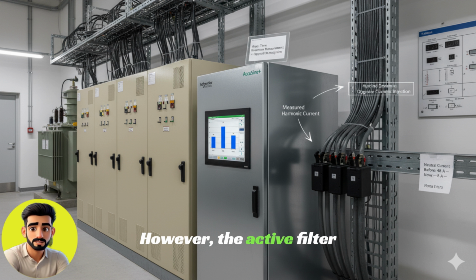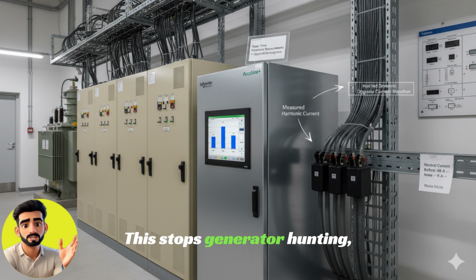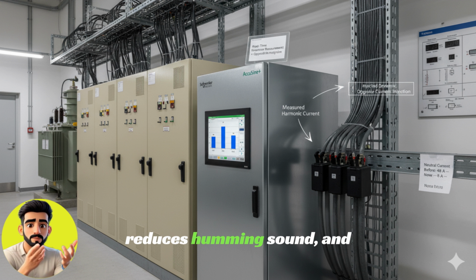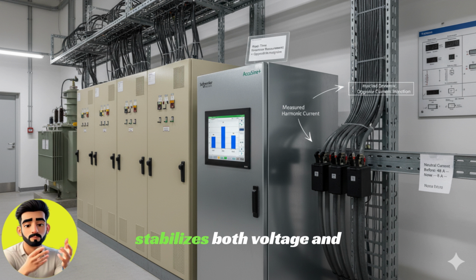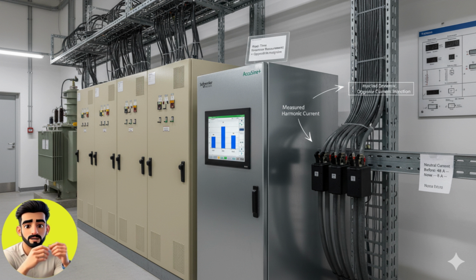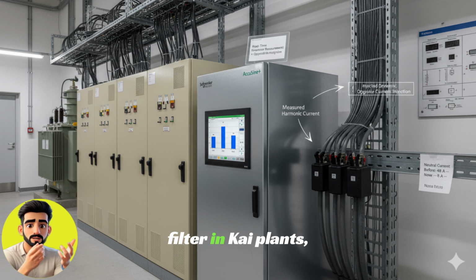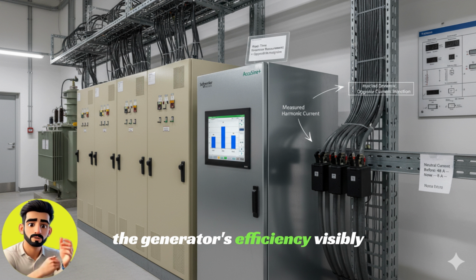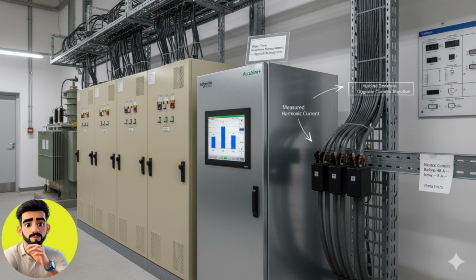However, the active filter provides smooth, clean current supply to the generator. This stops generator hunting, reduces humming sound, and stabilizes both voltage and frequency. After installing the active filter in such plants, the generator's efficiency visibly improves.